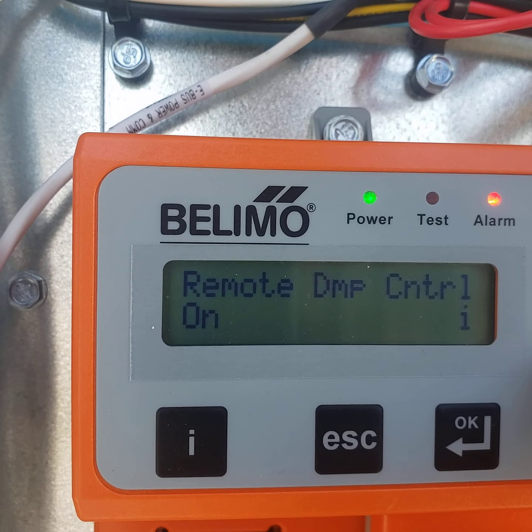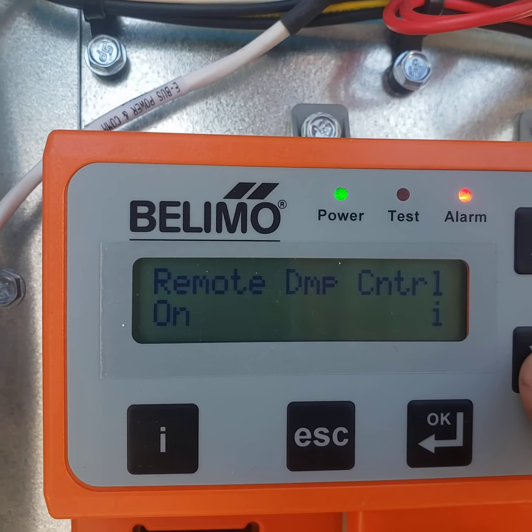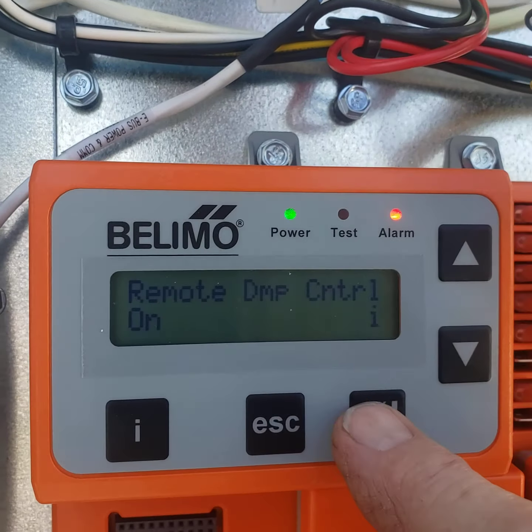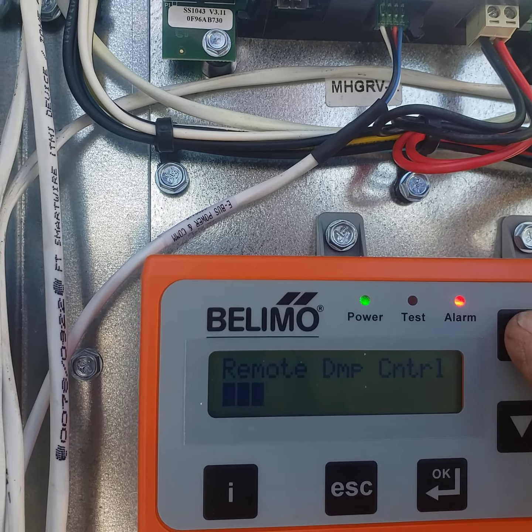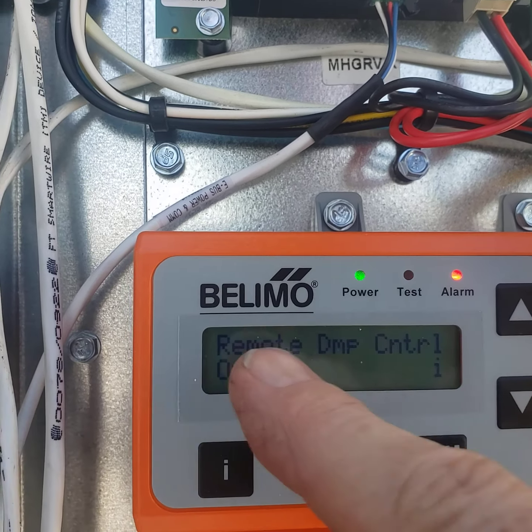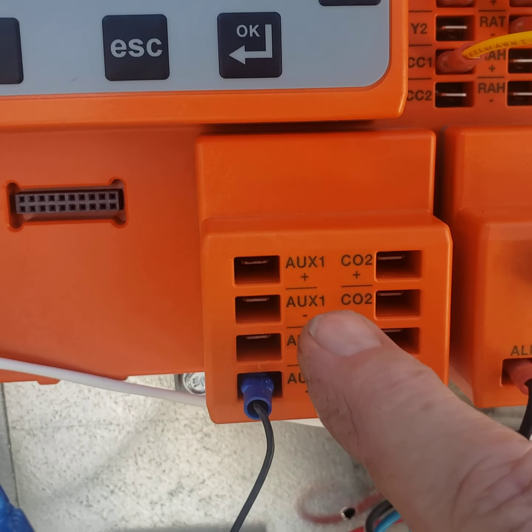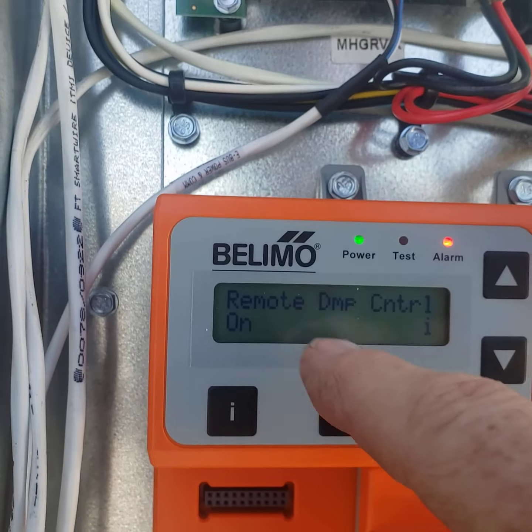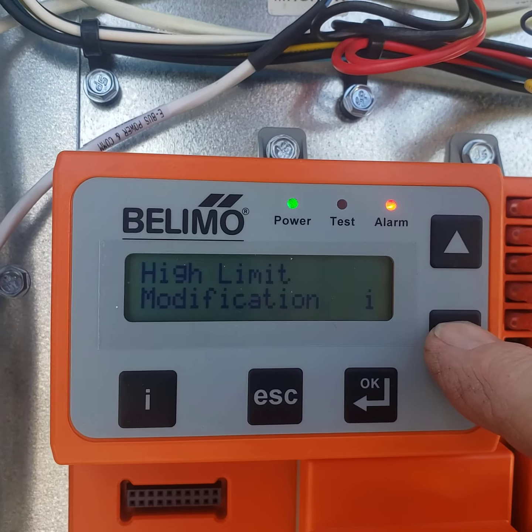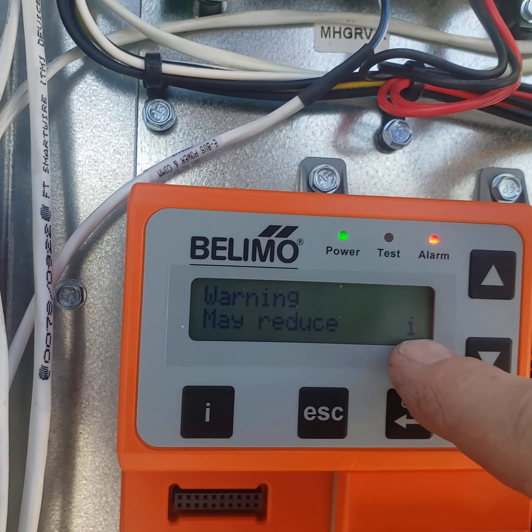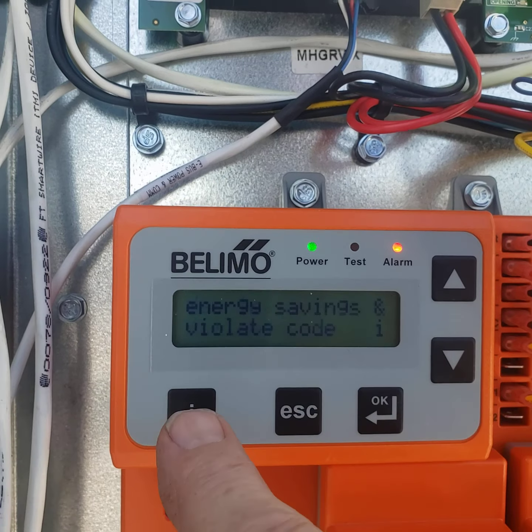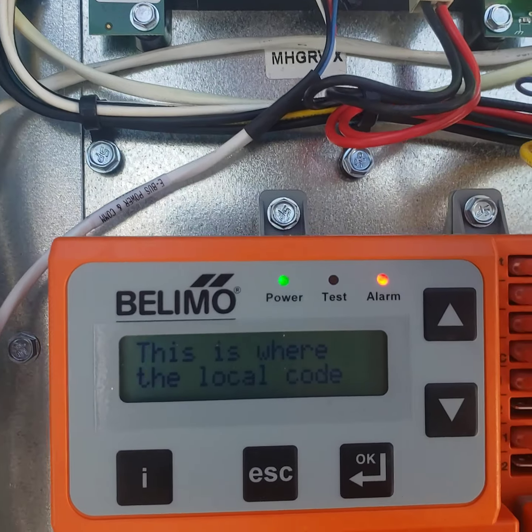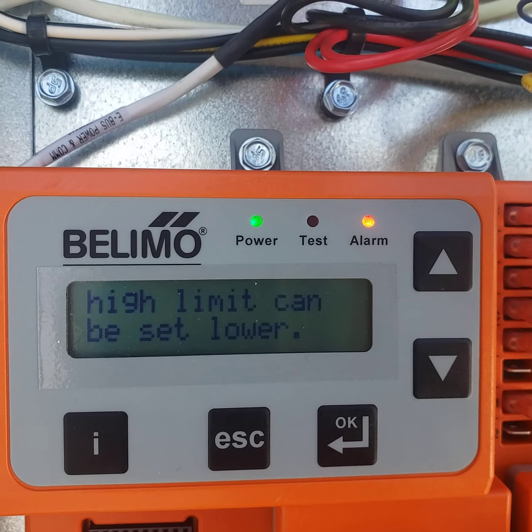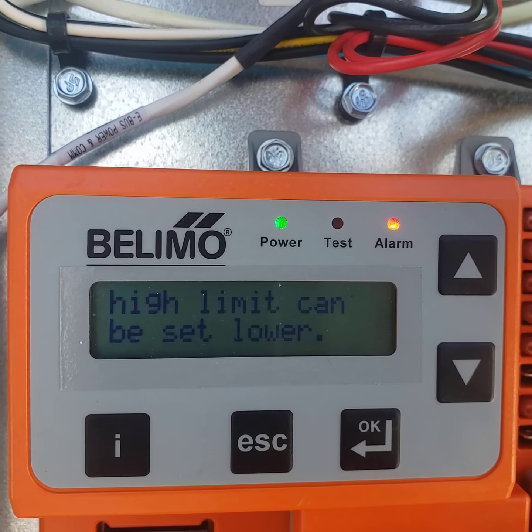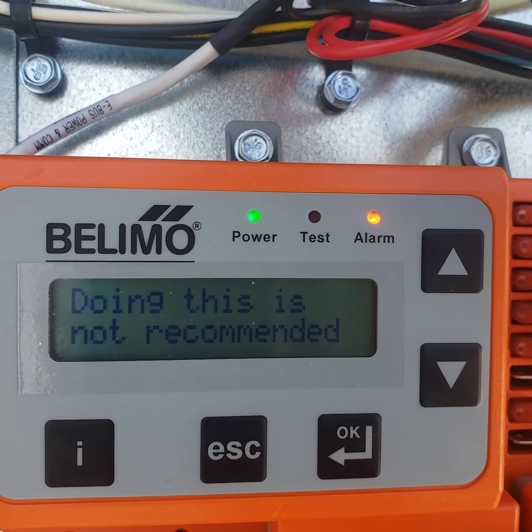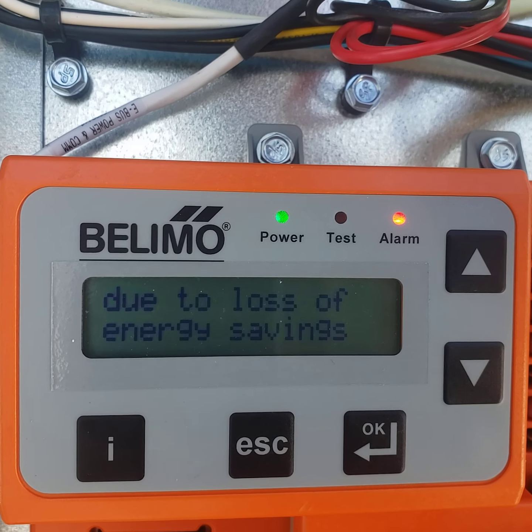Purge enable, we're not doing purge. Remote damper control is on. That's a selectable item. We can change that off or on. It's on, and like I mentioned before, that's what we're doing here. So to enable that, you have to go in here. High limit modification. Look at that. The little I there means that you can hit this I button to get information on what this does. This is where the local high limit can be set lower. Doing this is not recommended due to loss of energy savings.